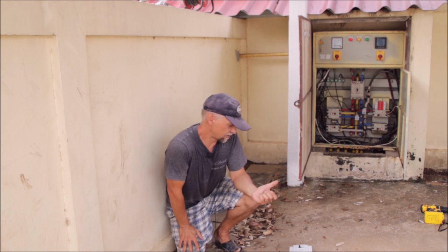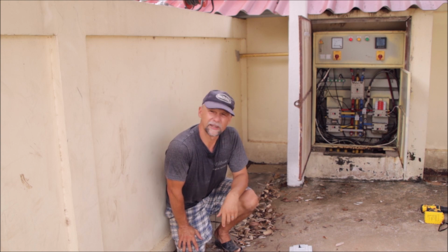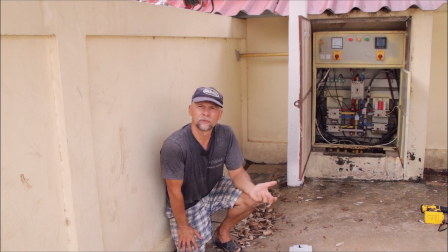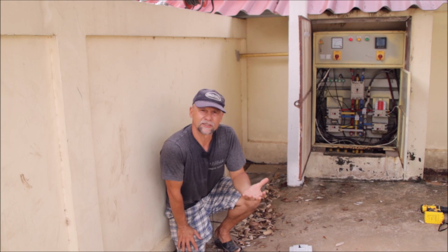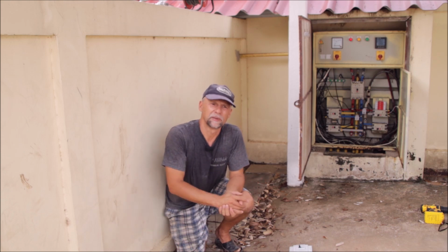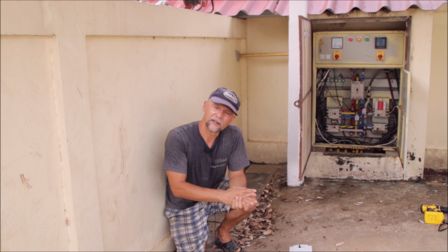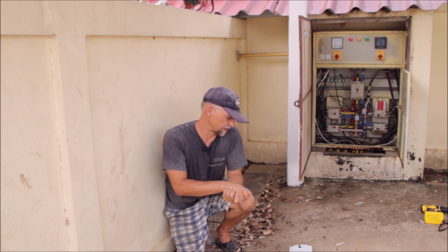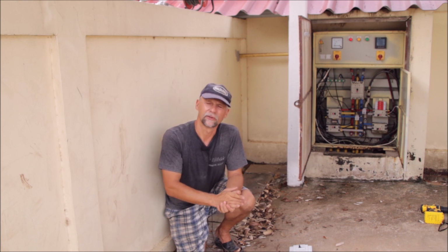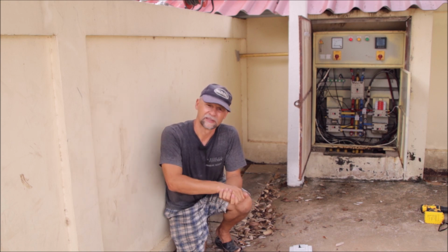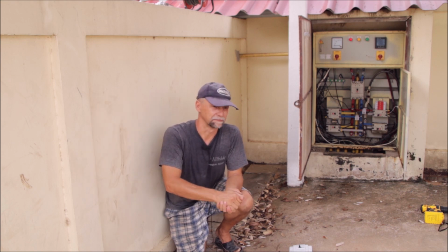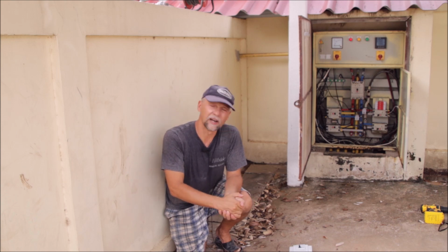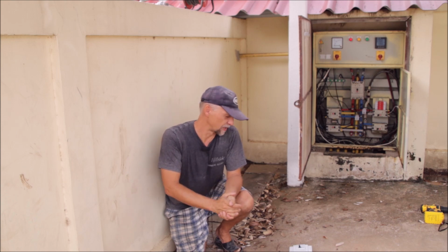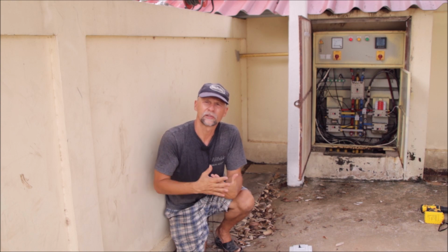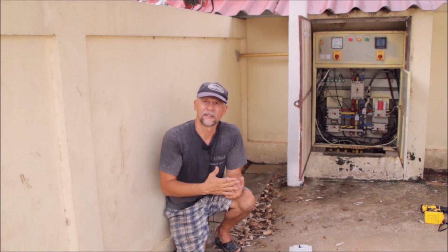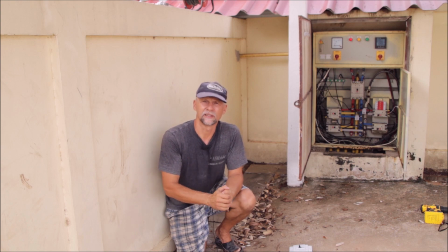So changing this breaker from 100 to 80 has nothing to do with our new line here. I just want to increase the buffer from around 5.5 times the nominal current to 7 times the nominal current, and the restricting cable is still the one to the main building. 80 amps is still enough for the load, so this breaker will not be overloaded. Overload protection, leakage protection, those kinds of things are always taken care of inside the load centers, right?